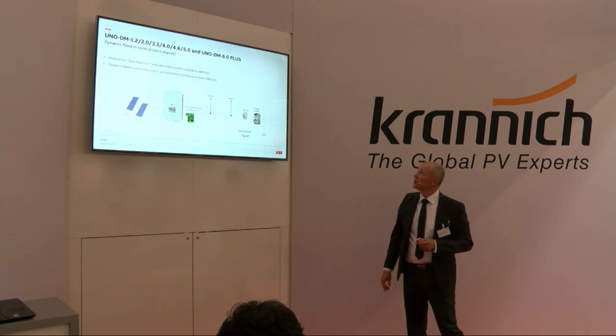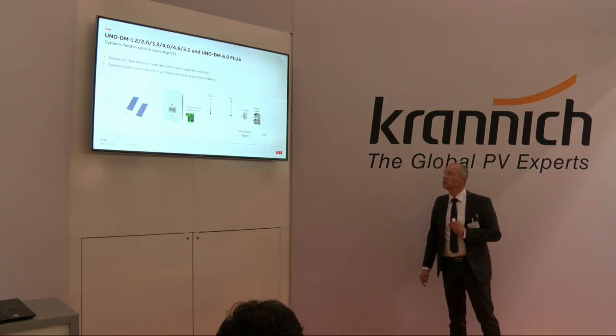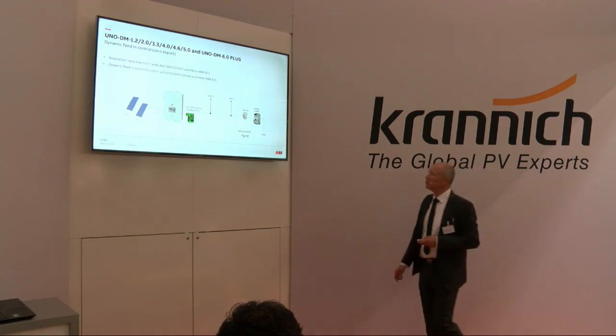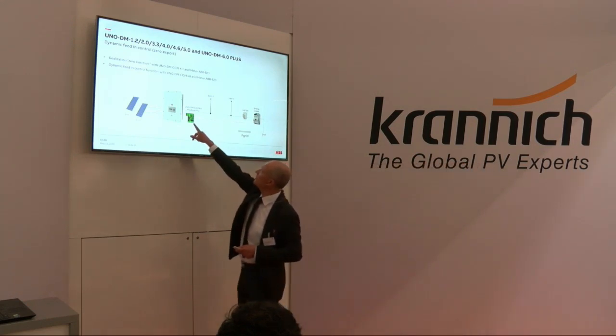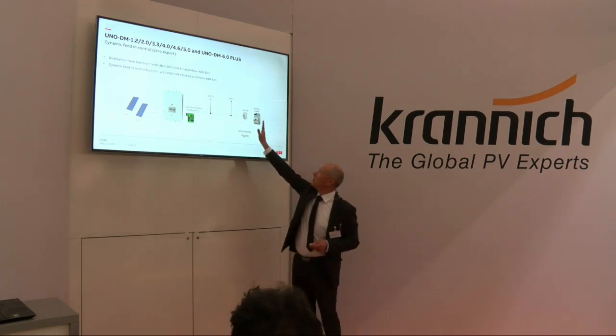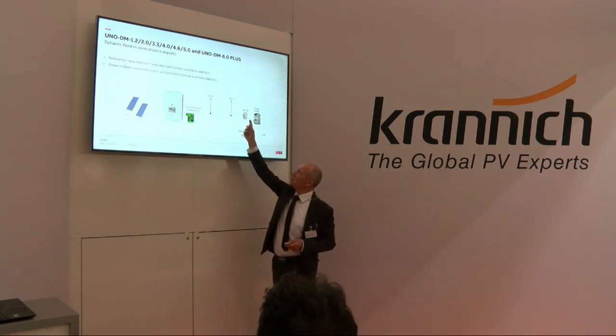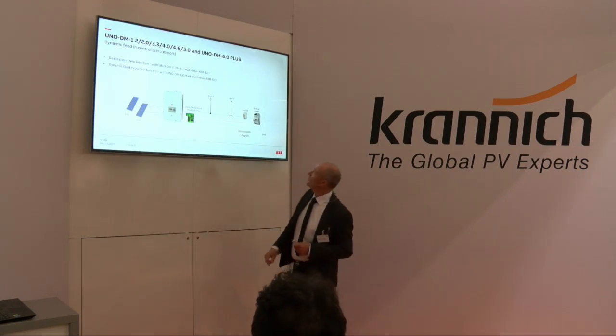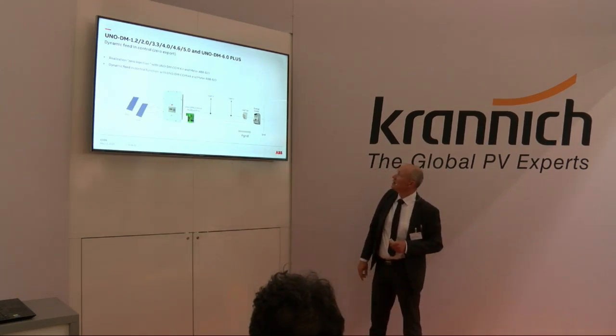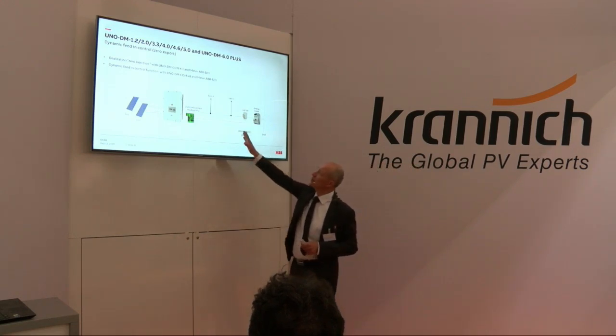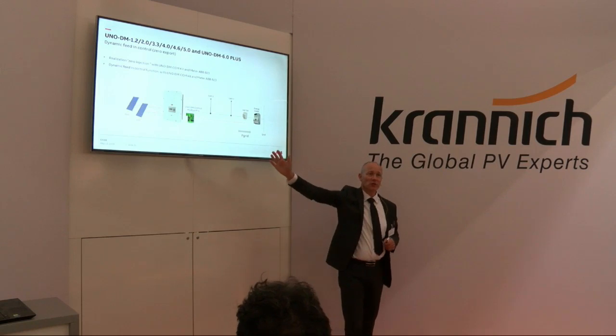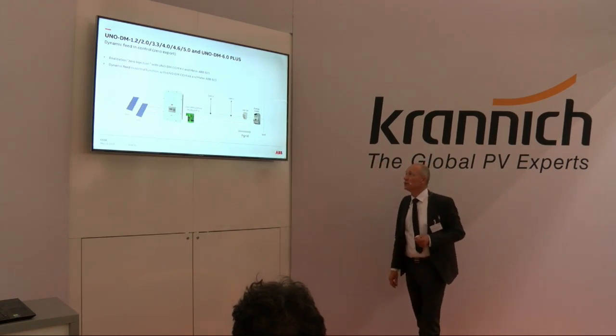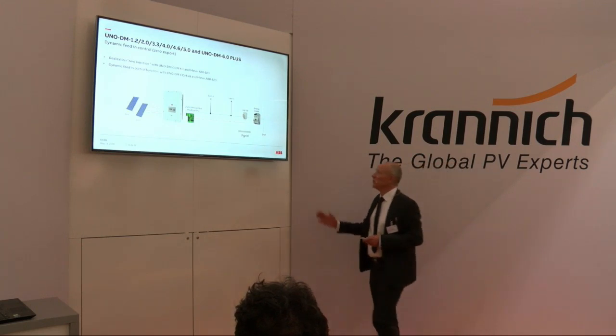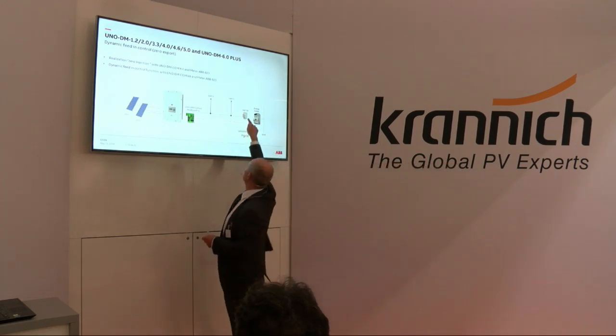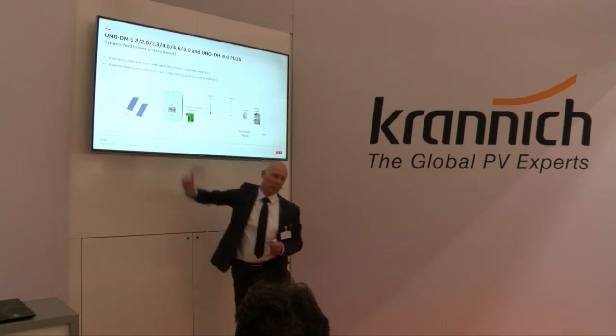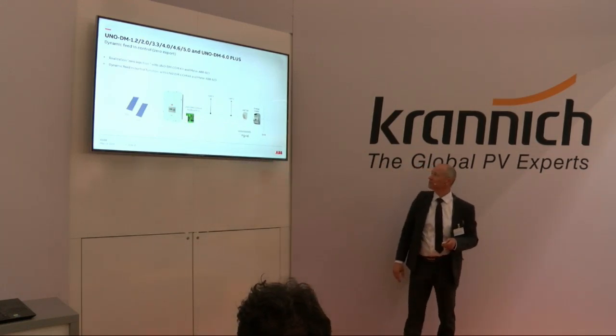Let's have a look at the dynamic feed-in control, or you can also do zero export. This is the application note for this. You have the inverter, you need this special card, and then you have the energy meter. This gives the feedback to the inverter based on Modbus RTU, and then you can define if you want dynamic feed-in control or zero export. So a very easy one. This interface is combined. That's an ABB product, so no problem at all.